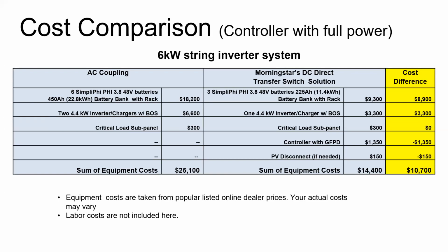With the MorningStar DC Direct transfer switch solution, we have the ability to choose how much PV we use. Even with the controller at full power here, we'd only need 3 batteries in this case, and only 1 inverter, so the cost actually comes out lower. We don't need to worry so much about the array size, since we can limit what it pushes into the battery. That'll make more sense in the next example.